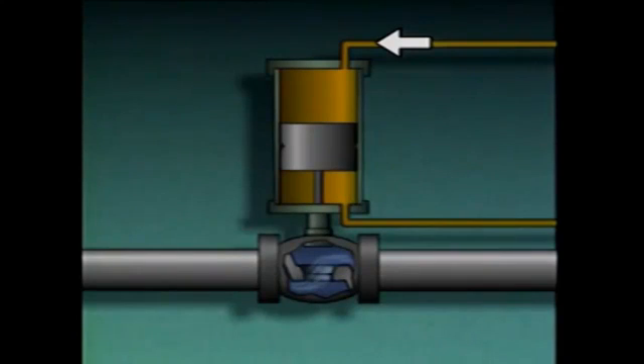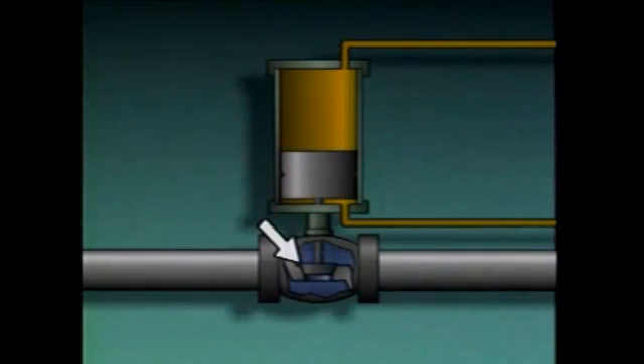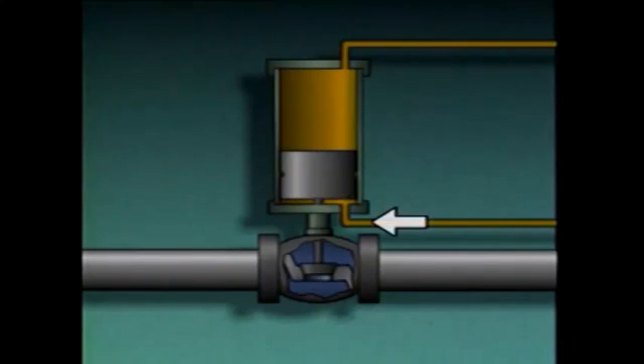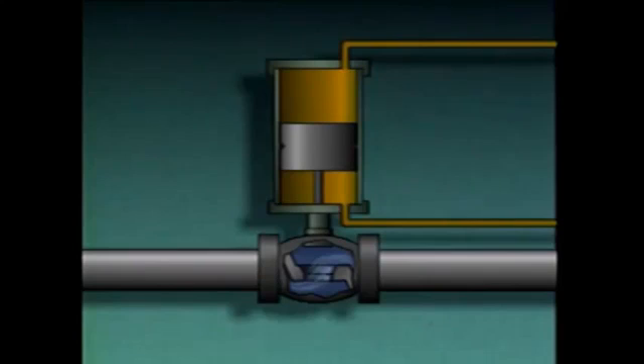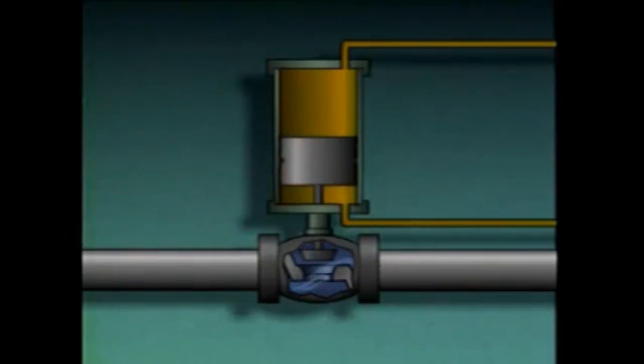If fluid enters through the top port, it pushes the piston and piston rod down to close the valve, and an equal volume of fluid is bled through the lower port. When fluid is directed into the lower port, it causes the piston and piston rod to move up, opening the valve, while an equal volume of fluid flows out of the upper port. When fluid flow is stopped, fluid is trapped on both sides of the piston, holding it in place. The piston can be positioned anywhere by controlling the amount of fluid entering one port and bled from the other.